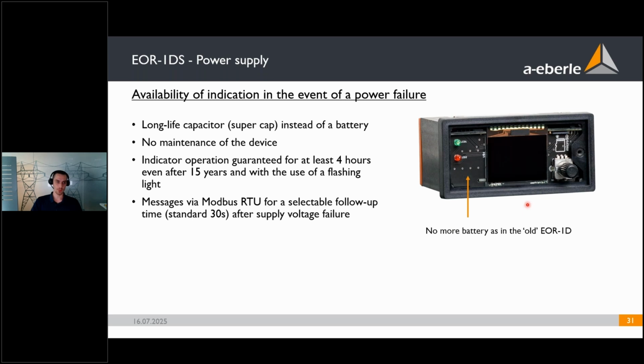The indication via Modbus RTU is not available for 4 hours, but it's selectable for a follow-up time. Standard would be 30 seconds after supply voltage failure.